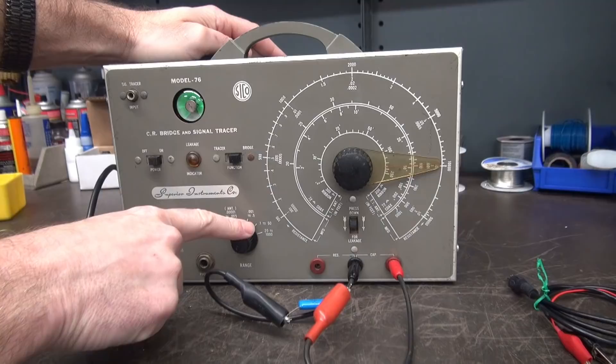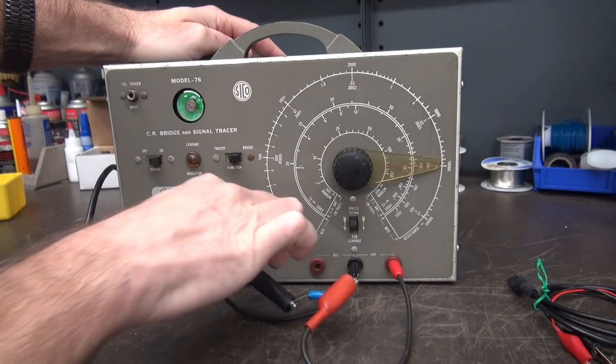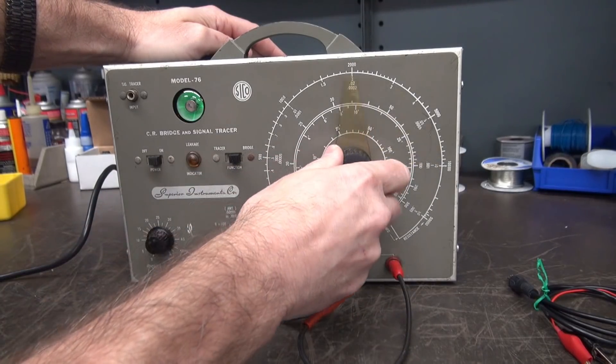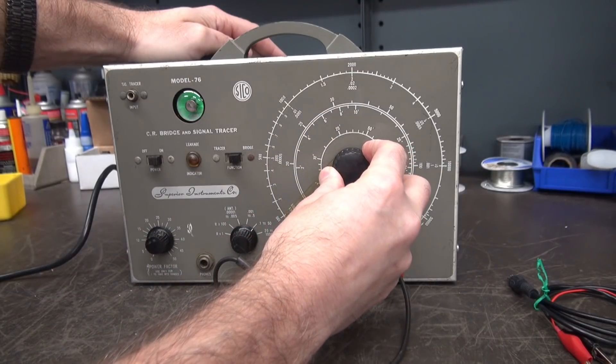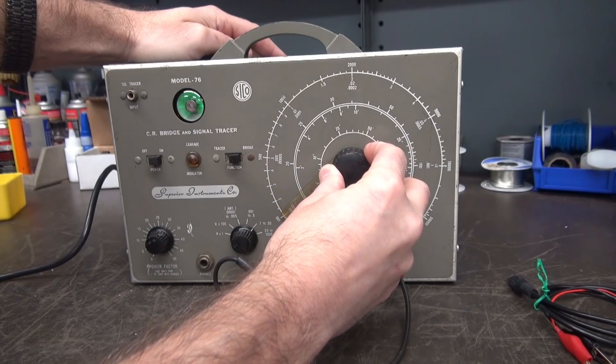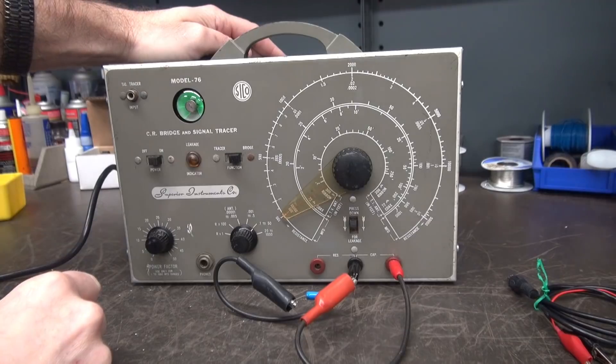So, the other range here is 0.1 to 50. So, if we go there, 0.1 is way over here. Let's see if it's there. Yep. Right on the money. Calibration looks good.